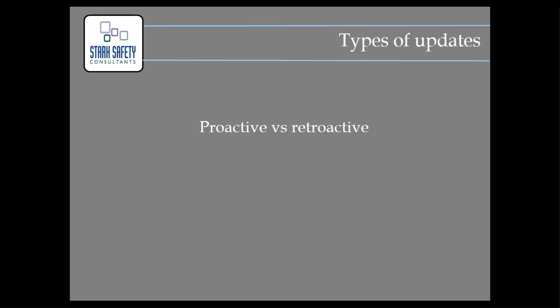Model checks versus system update. Model checks, again, are just targeted checks where we can look at just a segment of the model and verify if there's something that could significantly affect the system. And there again, with the proactive updating, putting something in the model, it's still there. It may not be a major impact, but we've taken the time in small increments, 5, 10, 15, 20 minutes is all we're talking about, to add some different components into the model, so at least it's in the one line. Even if we're not doing a full update, we can at least print out an update to the drawing and have a clean copy that people can then continue to use and is a lot easier to interpret.